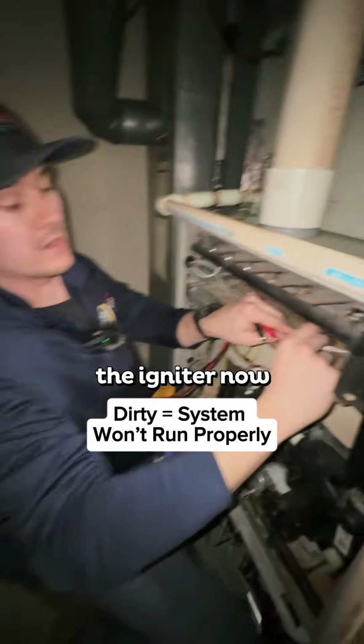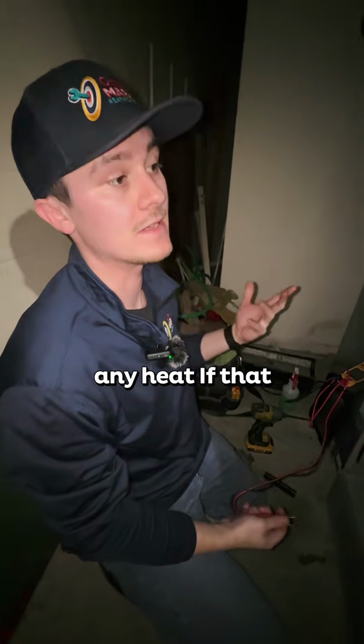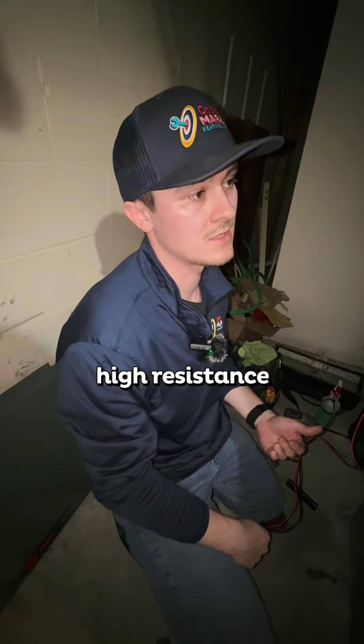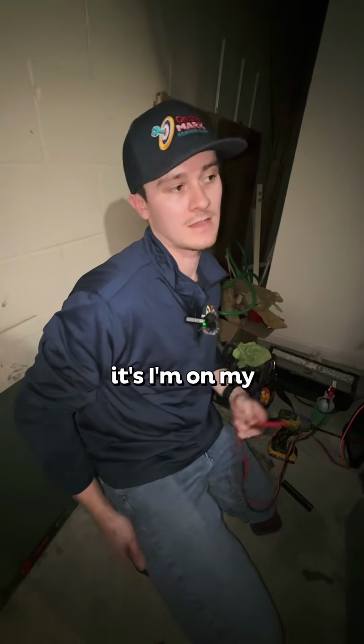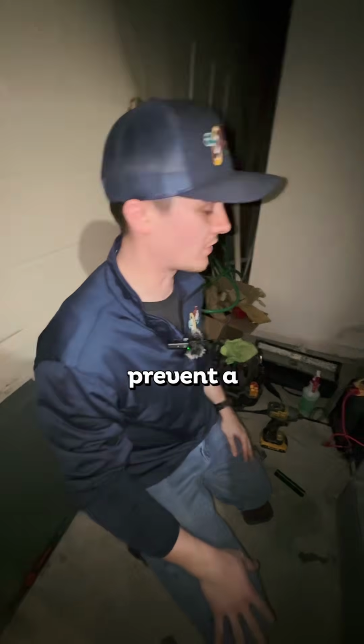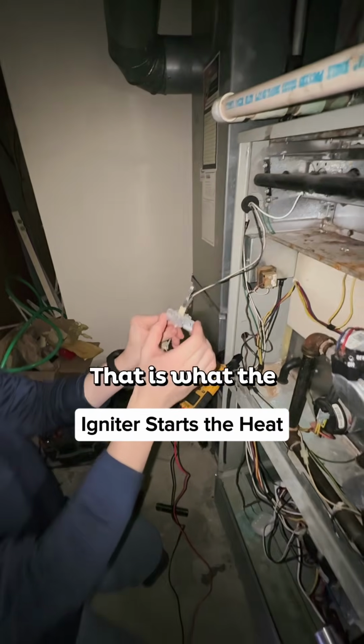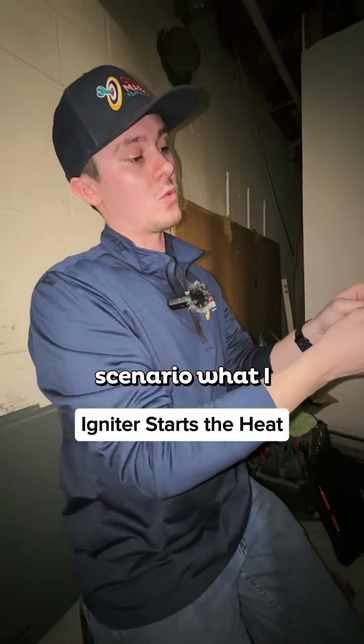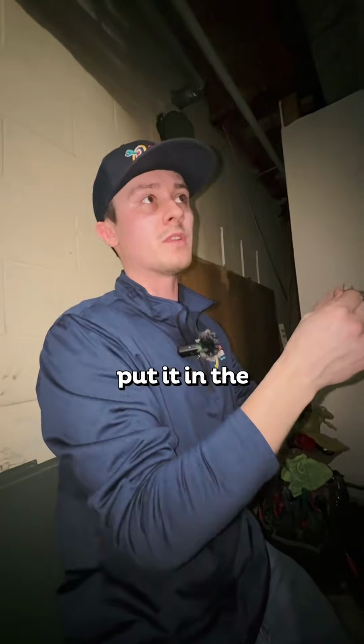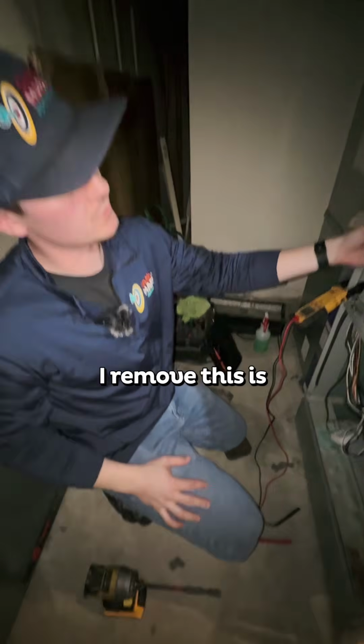So I'm checking the igniter now. Without the igniter, you don't have any heat. If that igniter has too high of resistance, it may still be working, but it can tell us, hey, I'm on my way out. We would recommend replacement to prevent a breakdown. I also like to do a visual inspection. That is what the igniter looks like on this specific furnace. So in this scenario, what I would put this down as is a yellow. Chances are this is original. I'd put it in the yellow, letting the customer know, hey, it's original. This is called the limit switch.